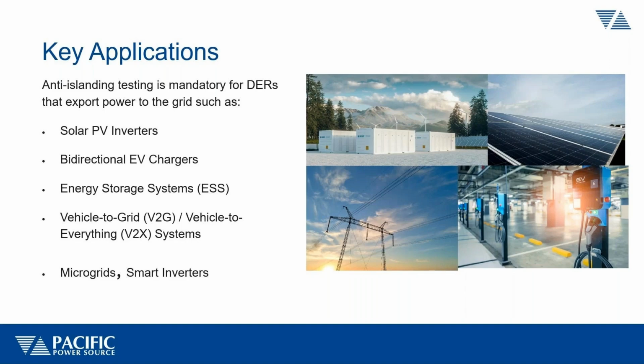And examples of DERs are listed here. Obviously, solar inverters are very common. EV chargers are more and more becoming bidirectional in the last few years. So they are now essentially also considered DERs when they are plugged into a bidirectional charger at home or at another facility. And as such, they are potentially energizing the grid as well. When there is a power outage, they also need to meet these anti-islanding requirements. So the demand for this test has grown from just PV inverters to also more and more include EV chargers, bidirectional chargers, both onboard chargers as well as home chargers that are often used in combination with a battery backup system to provide backup power when the grid disappears by using the battery in the car as storage.